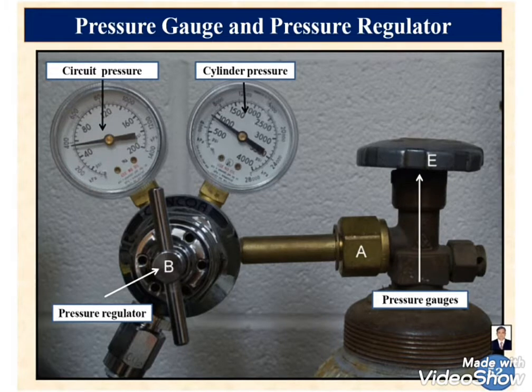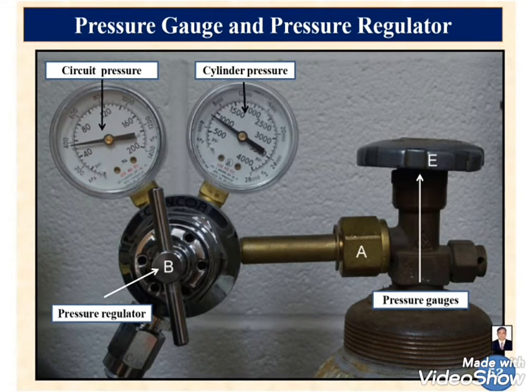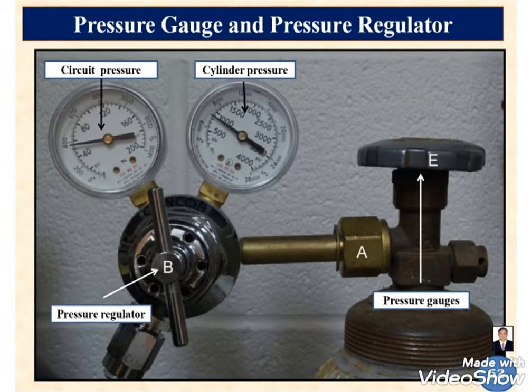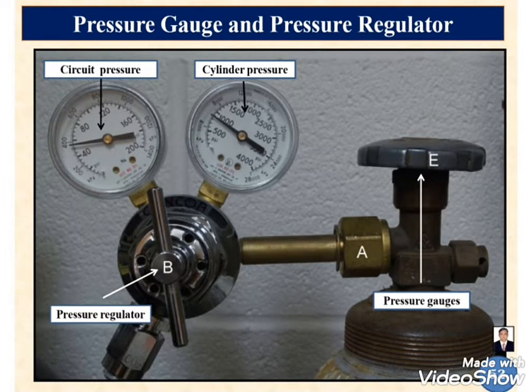The next dial is the pressure regulator dial, meaning the pressure reducing valve. It converts the high pressure into low pressure and allows oxygen toward the patient at only 40 to 50 psi. The full bottle has 2200 psi, so this is a high pressure system. Our animals, even human patients, even canine patients cannot tolerate these pressures. Animals' lungs tolerate only 40 to 50 psi.